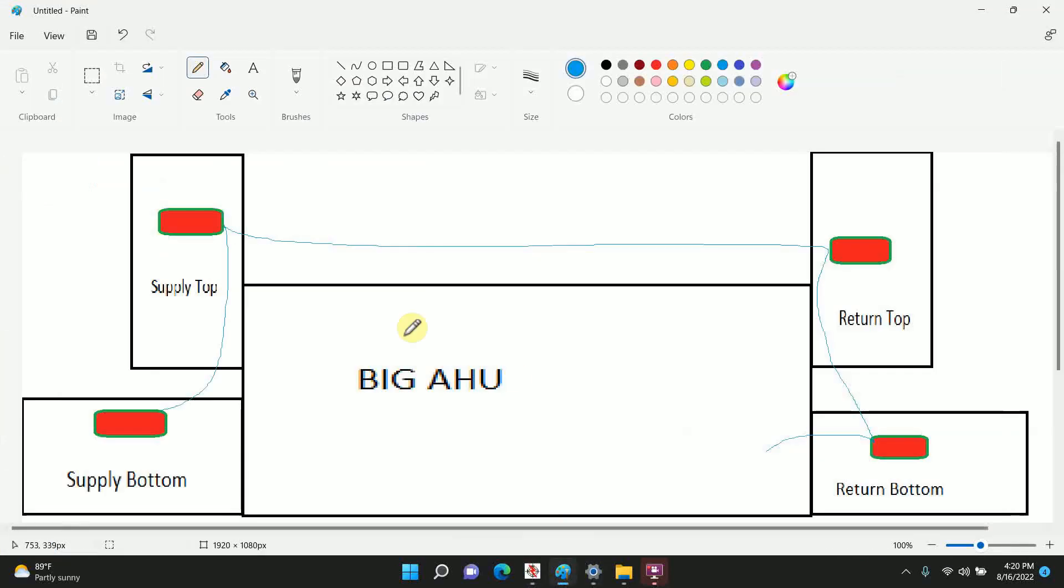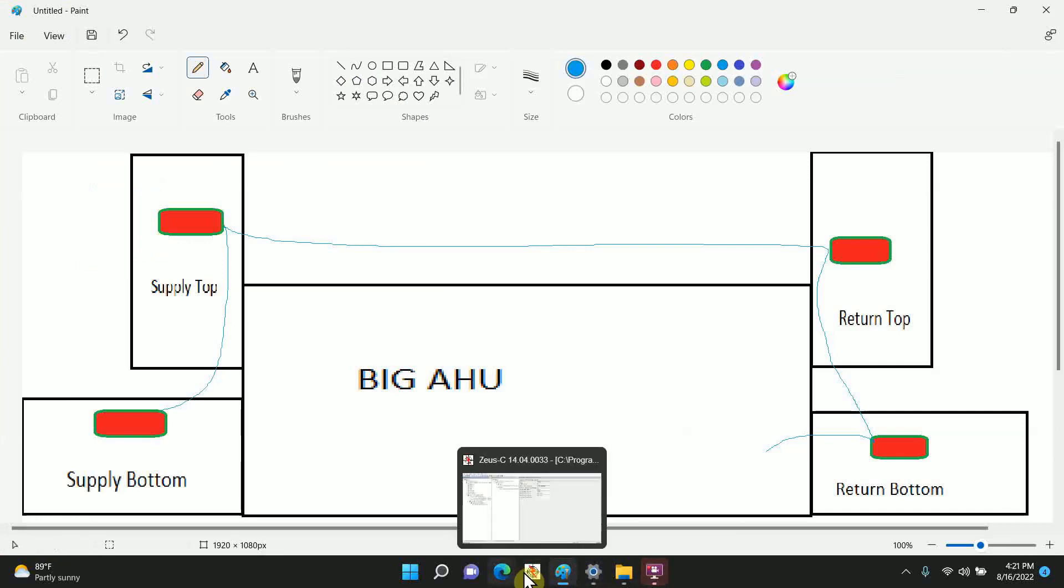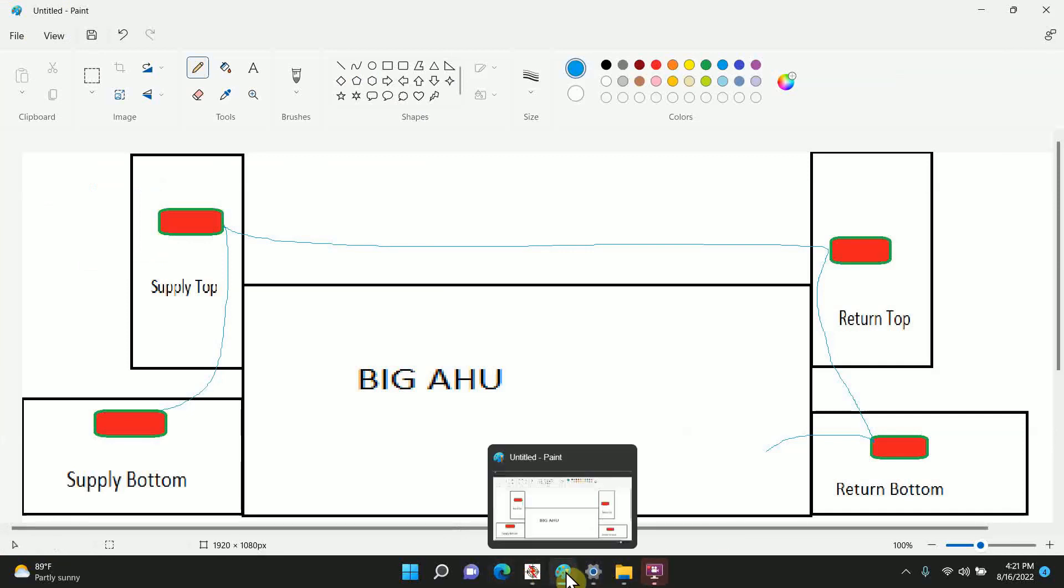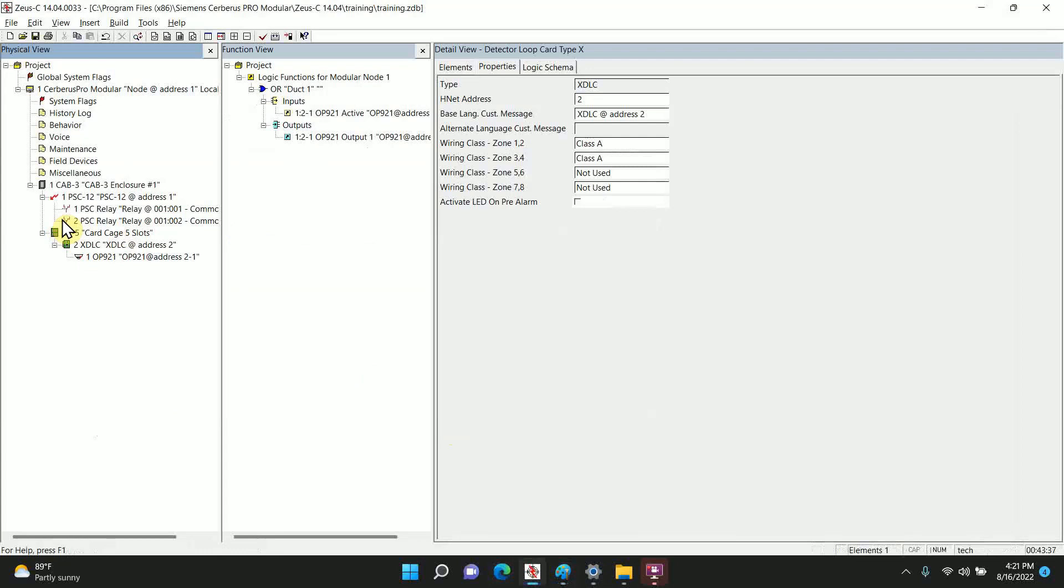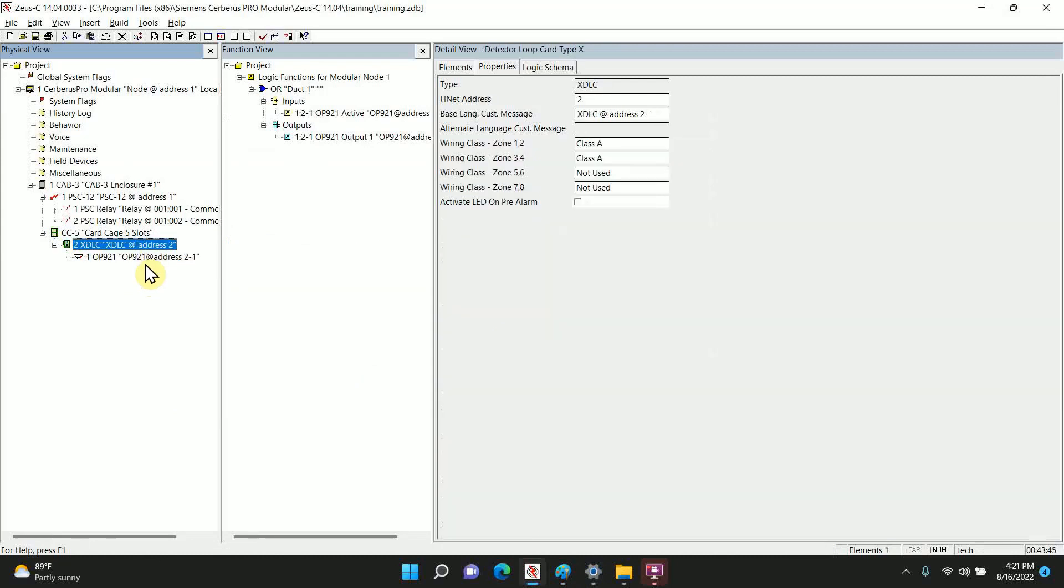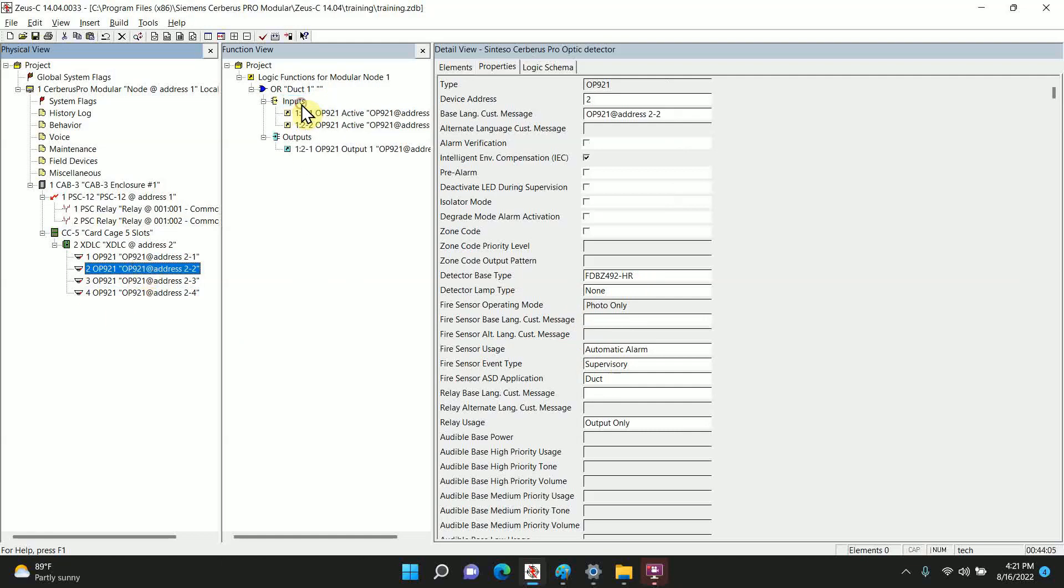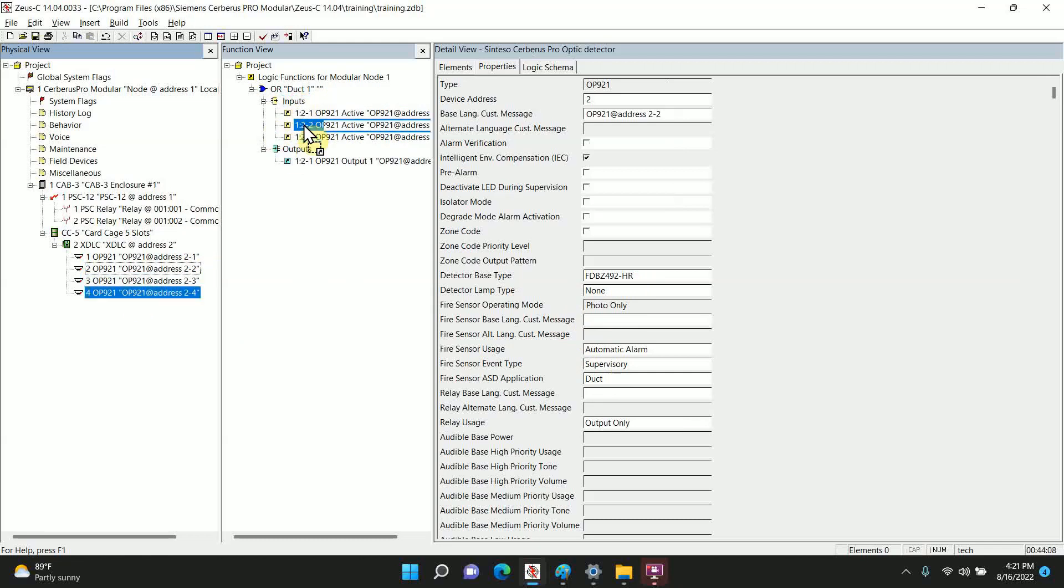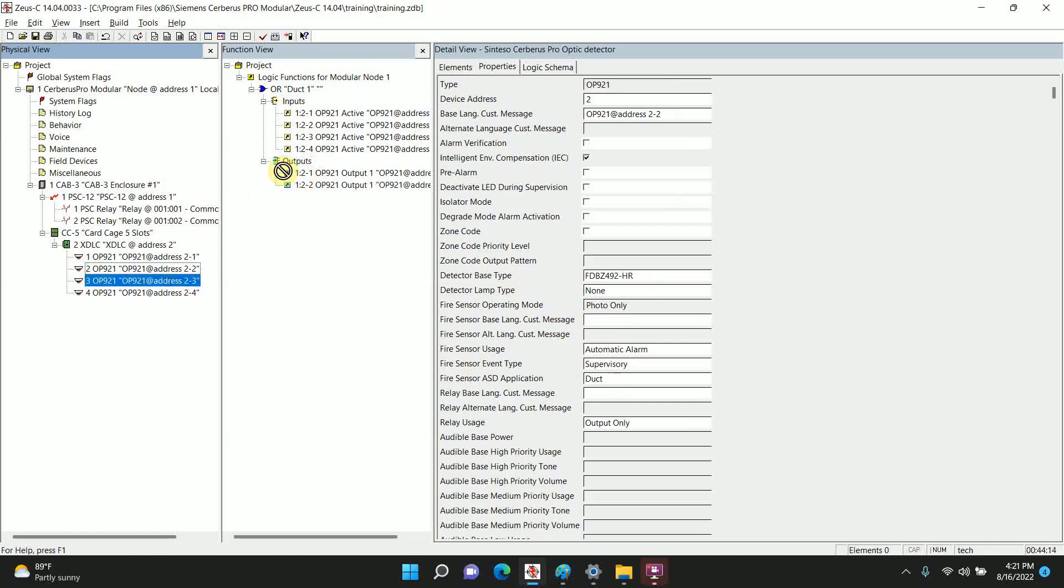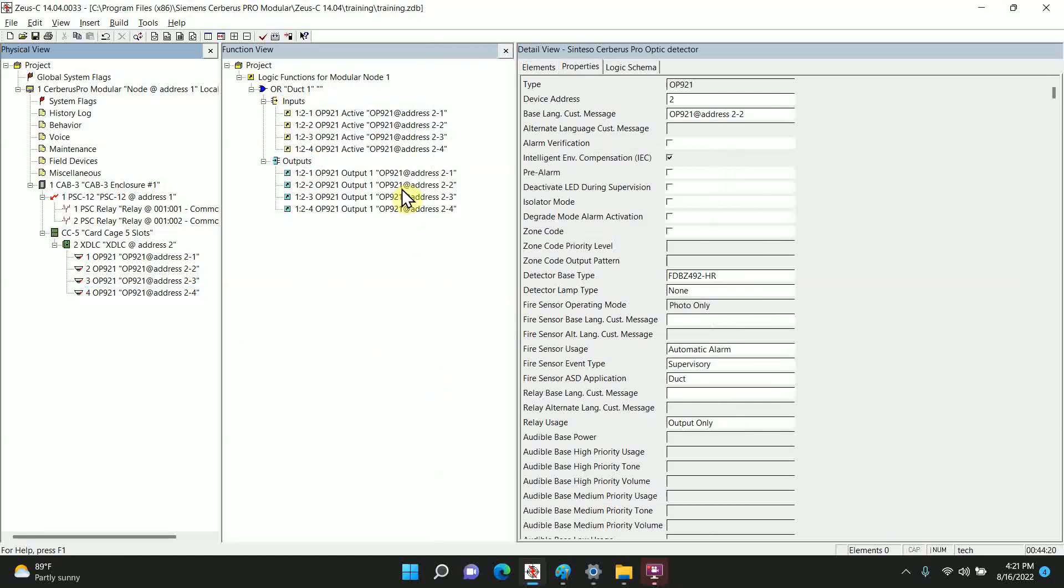For our example again with the four, we're going to add in the other three and show you just how simple it is. Let's go back to the XDLC. Please note that you can use copy and paste in this, so I'm going to do a control-C and paste it three more times. I'll address 2, 3, 4. If you notice, it does have the FDBZ HR in there, it does still have duct, it does still have supervisory. So we're going to make any one of these trigger all four of the relays, so we're just going to drag and drop again. And you can drag and drop again for the outputs. With that, any one of those duct detectors will trigger all four relays at the same time.